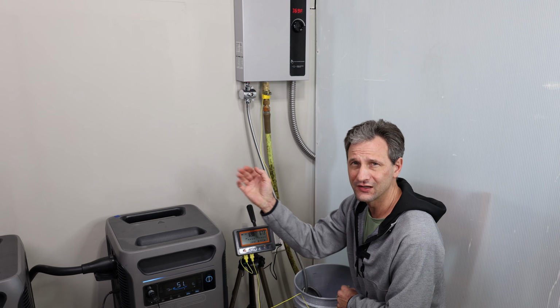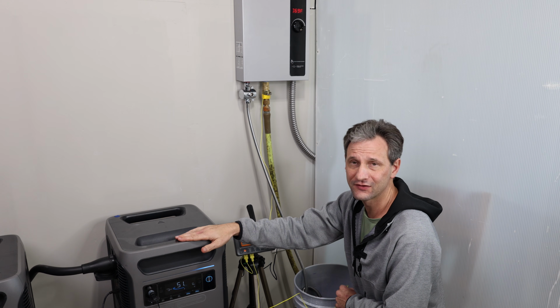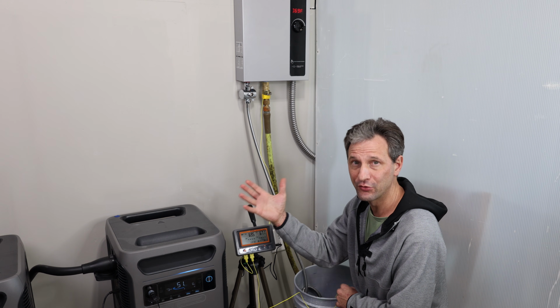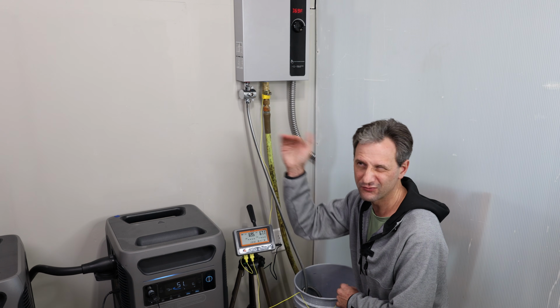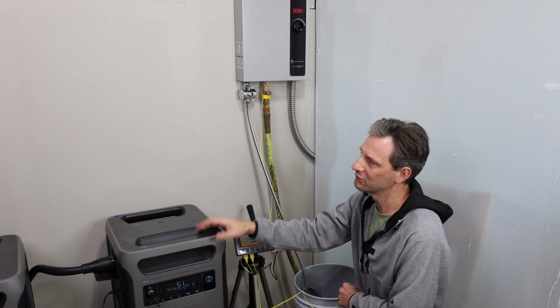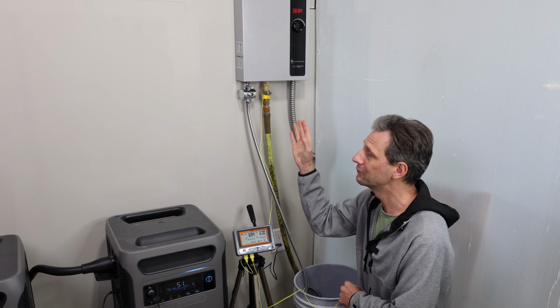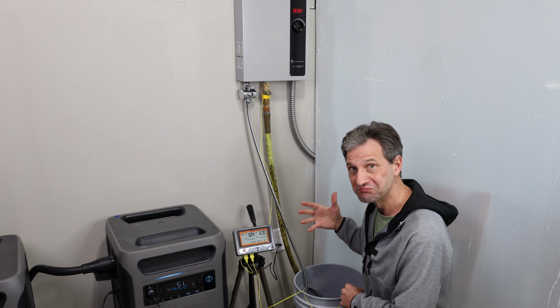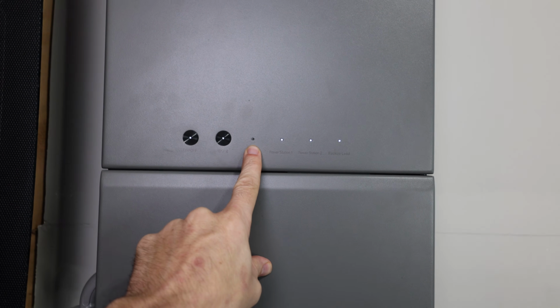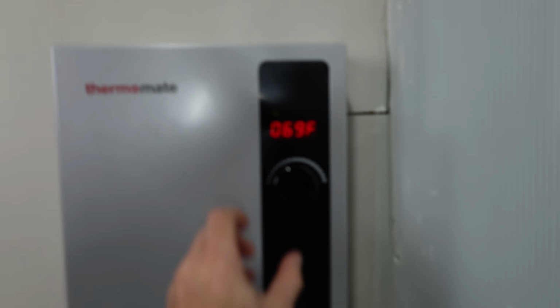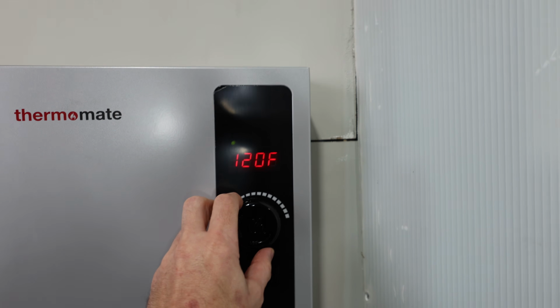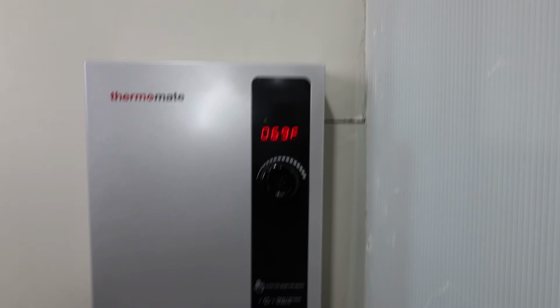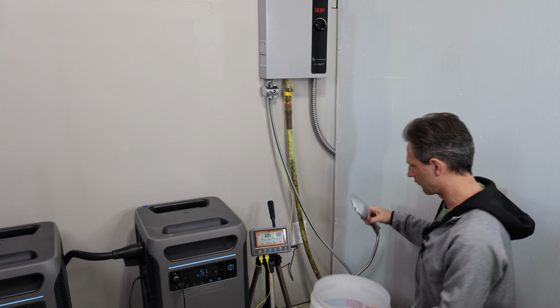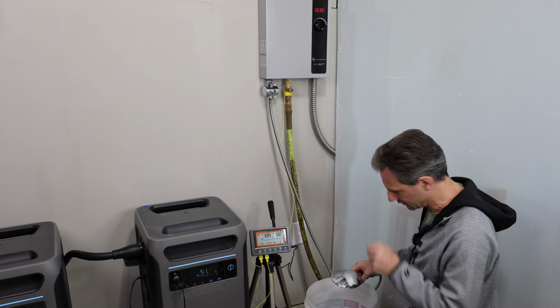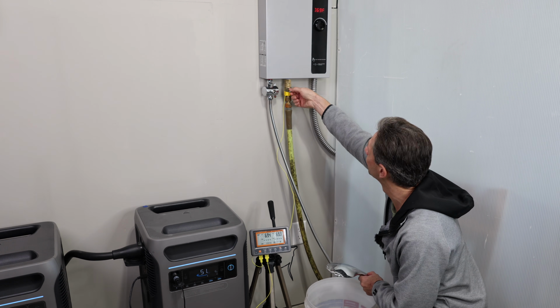Now, 11 kilowatts is 1 kilowatt below the max for these 2 units. The 2 together should be able to deliver 12 kilowatts and a little headroom for surges. So I think it'll power it without a problem. But is it actually going to heat the water? Let's see. All right, you can see the light is off for grid input, so we're running only off a battery. Let's set our target temperature to 120 degrees. I'm going to start with this bucket till it starts warming up, and then we'll switch to the one that I'm measuring with. All right, let's see what happens.